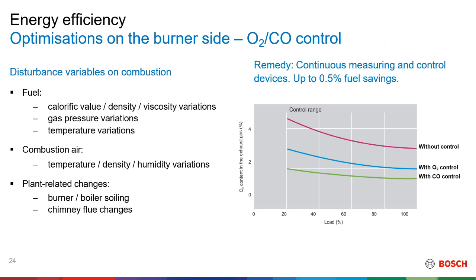Okay, on the right you will see a graph of the amount of O2, where the first graph shows a burner with no control. So this is just a burner with nothing monitoring the combustion process at the end. As you can see, the amount of excess oxygen is a lot. Just by adding O2 control, you're able to drop the amount of excess oxygen in the flue gas. And by adding CO control, you're able to drop the amount of excess oxygen even further. So having both O2 and CO control, you're able to optimize your combustion process. Okay.